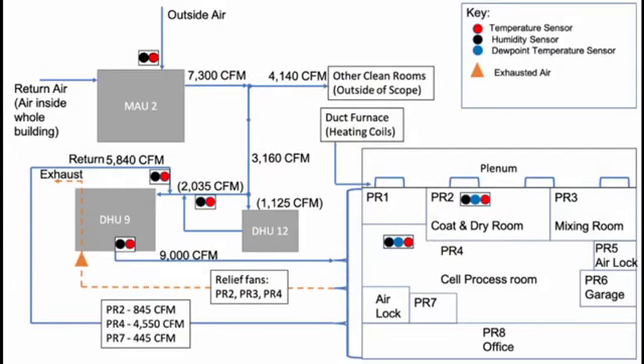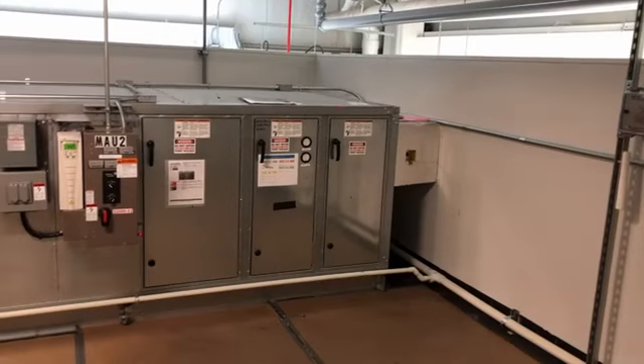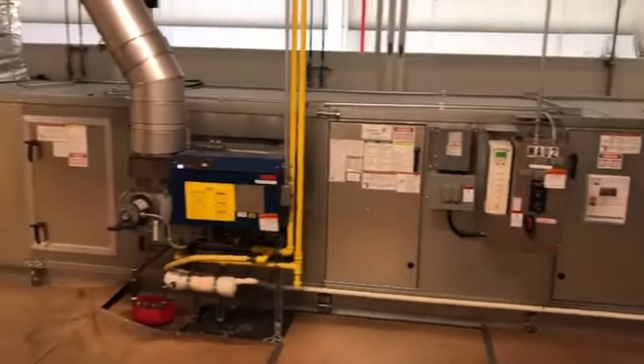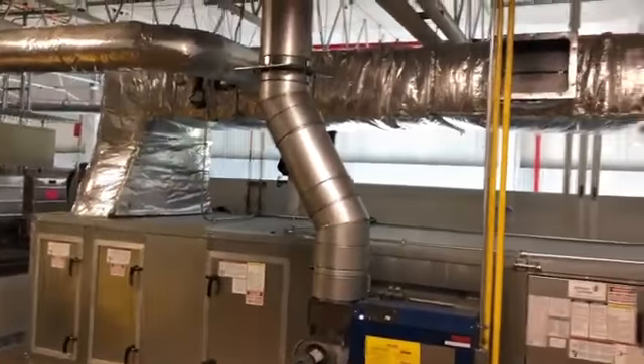So this slide shows the current system with the main system components, MAU2, DHU12, DHU9, and the main rooms in the pilot dry clean room, which are the cell process room, PR4, the coat and dry room, PR2, and the mix room, PR3. The makeup air unit takes air from either outside the building or inside the building above the mezzanine mechanical area. The intake air can vary greatly in temperature and humidity depending on the seasons and if it is coming from inside or outside the building. The MAU2 conditions the air by either heating or cooling the air to a set temperature. When cooling begins, this begins the process of moisture removal.